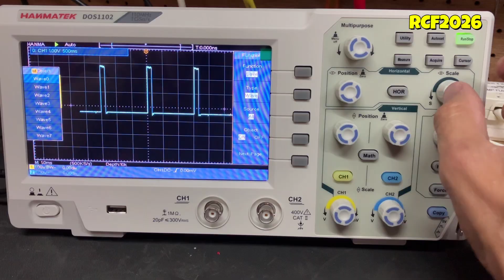If you want to capture a waveform and store it in the oscilloscope's internal memory, press the utility button and select Save. Using the available buttons, select Storage to save the current waveform. The waveform will then be stored in the DOS1102's internal memory for later viewing and analysis. You can save multiple waveforms, with each one stored as a separate waveform. The stored waveforms can then be individually selected and turned ON or OFF, allowing you to compare different captured signals on the screen.